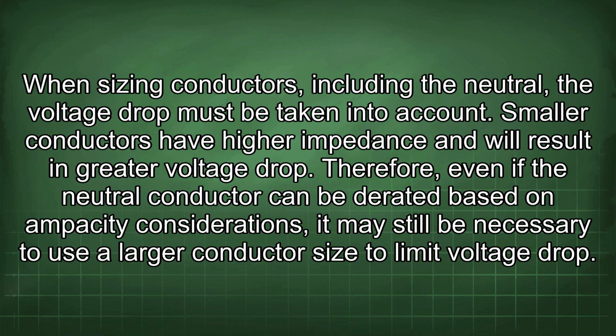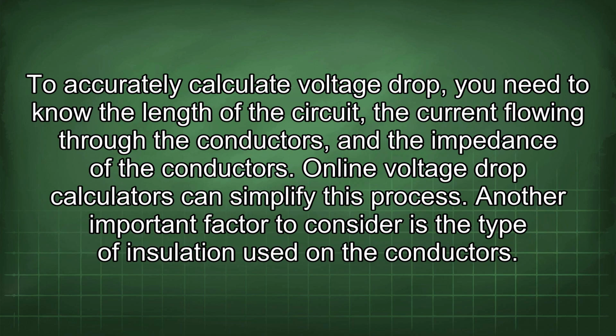Smaller conductors have higher impedance and will result in greater voltage drop. Therefore, even if the neutral conductor can be derated based on ampacity considerations, it may still be necessary to use a larger conductor size to limit voltage drop. To accurately calculate voltage drop, you need to know the length of the circuit, the current flowing through the conductors, and the impedance of the conductors. Online voltage drop calculators can simplify this process.